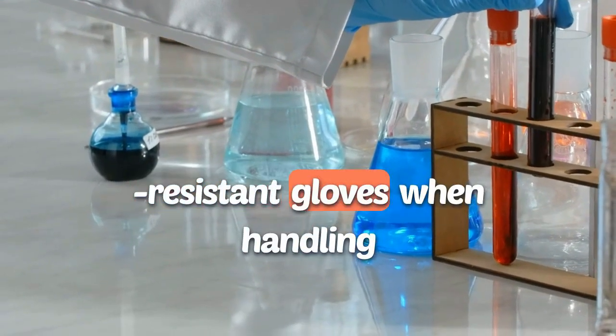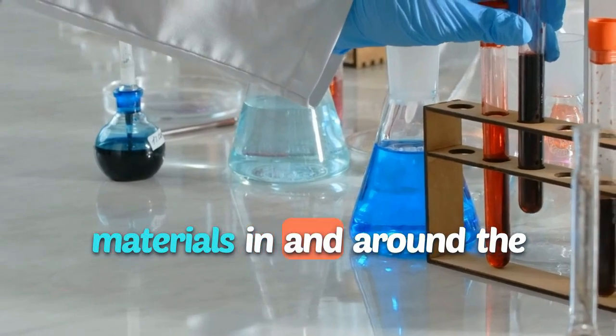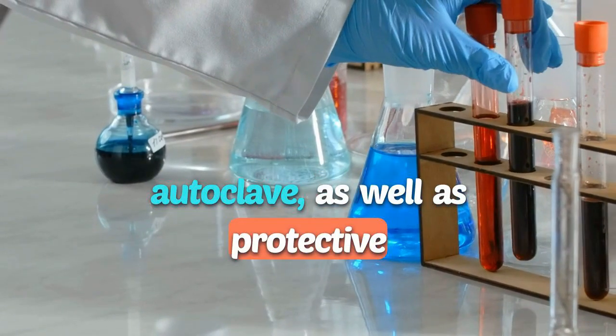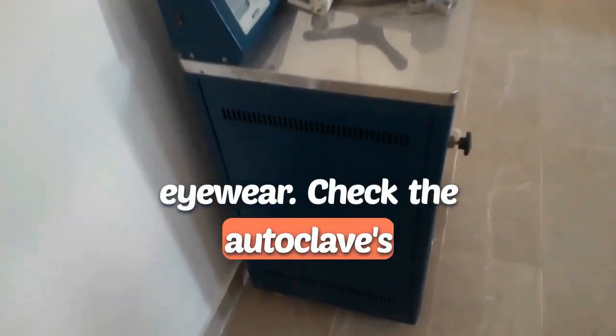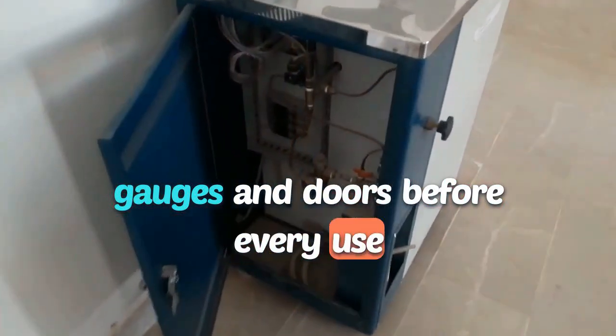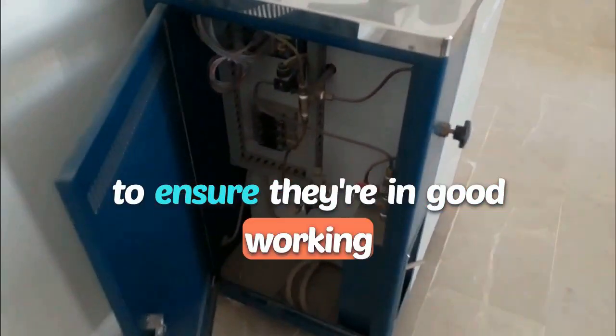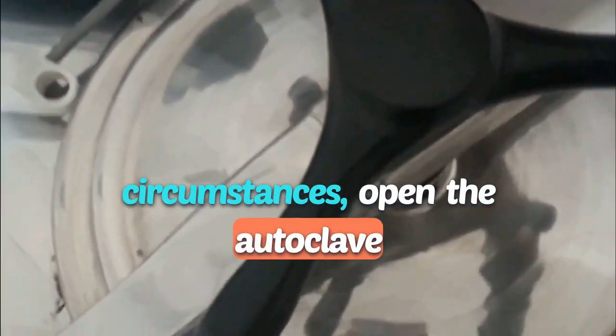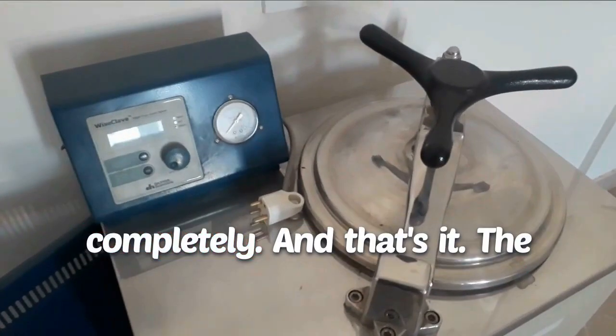Always wear heat-resistant gloves when handling materials in and around the autoclave, as well as protective eyewear. Check the autoclave's gauges and doors before every use to ensure they're in good working order, and never, under any circumstances, open the autoclave before it has depressurized completely.